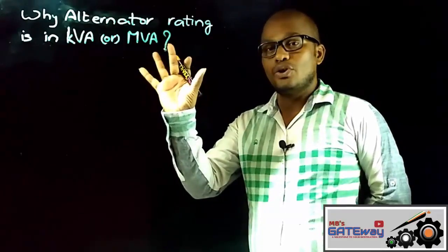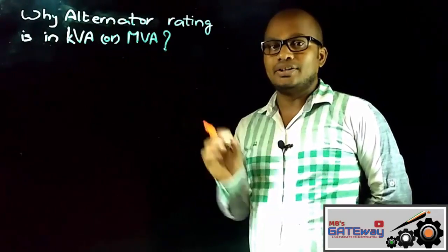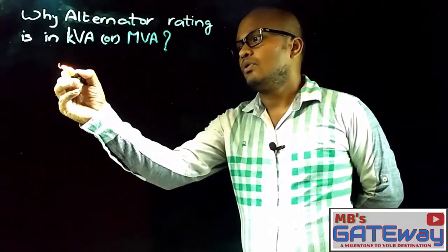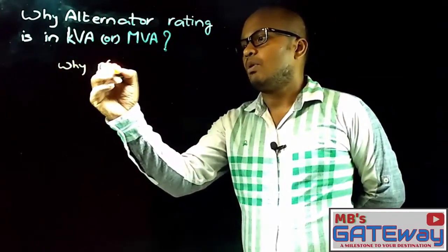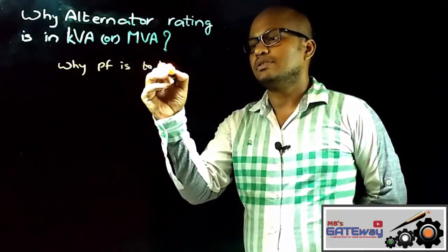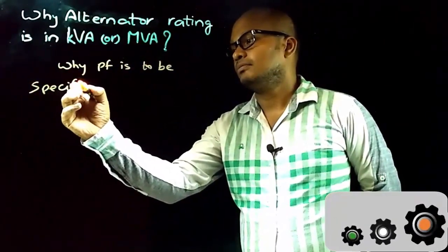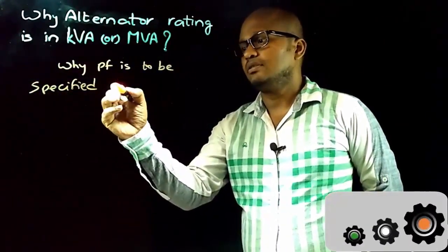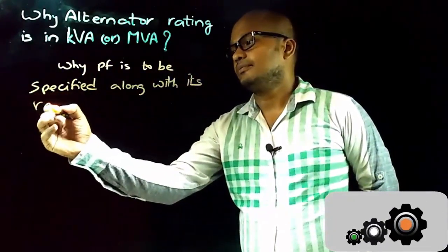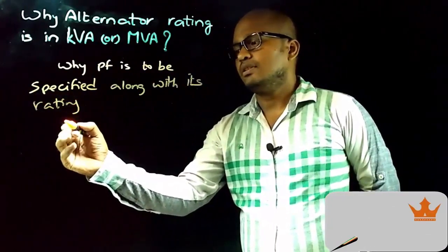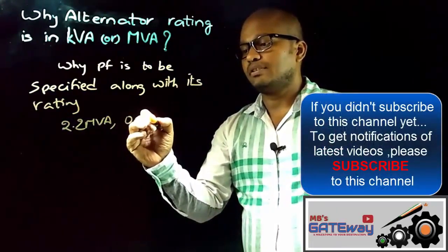Here is the important question on alternators: why is the alternator rating in KVA or MVA? From this discussion, you will come to know why the power factor of an alternator must be specified along with its rating — for example, if 2.2 MVA is specified, then the power factor must also be mentioned on the nameplate details.